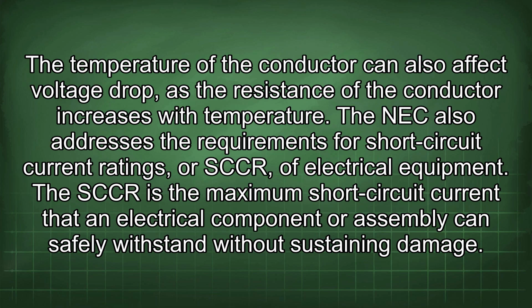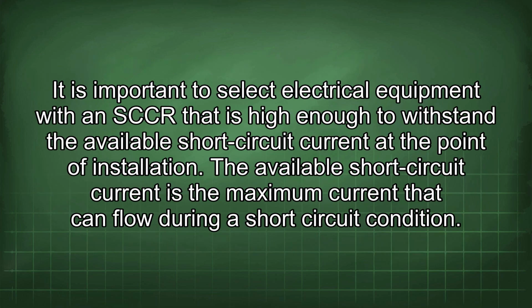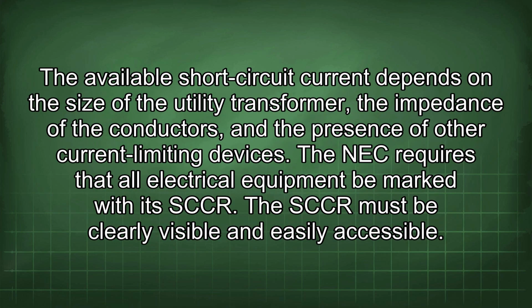The NEC also addresses the requirements for short circuit current ratings, or SCCR, of electrical equipment. The SCCR is the maximum short circuit current that an electrical component or assembly can safely withstand without sustaining damage. It is important to select electrical equipment with an SCCR that is high enough to withstand the available short circuit current at the point of installation. The available short circuit current is the maximum current that can flow during a short circuit condition. The available short circuit current depends on the size of the utility transformer, the impedance of the conductors, and the presence of other current limiting devices.